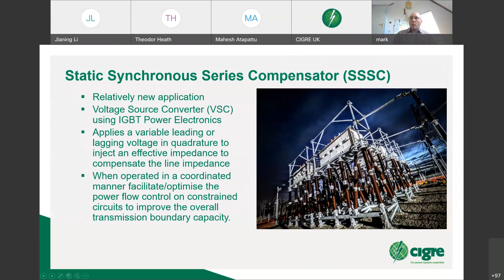So the technology, as you can see there, is essentially just boxes. If we go back to the previous picture, what I'm showing you here is everything inside this box. And then if you want more of it, you just add boxes in series. Hence why it's called the modular solution. What it consists of is a VSC valve, which can either inject leading or lagging vars. That has elements of protection around it.